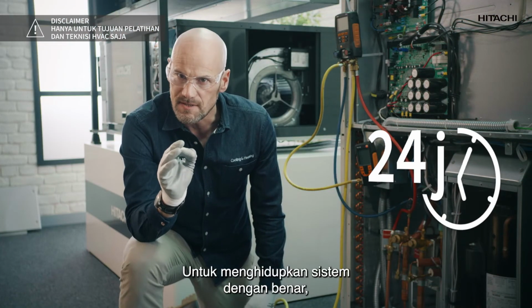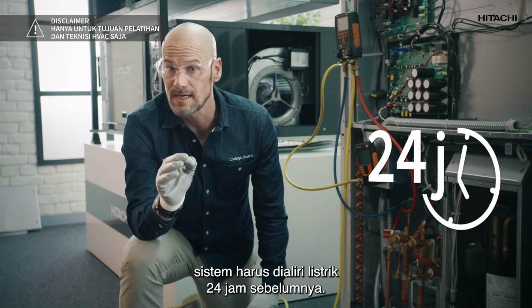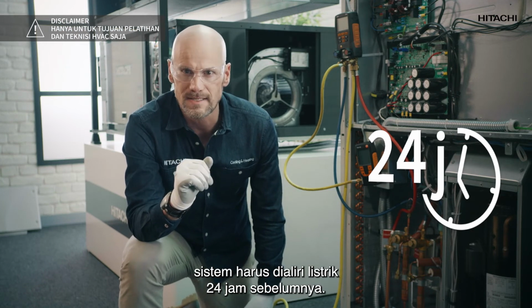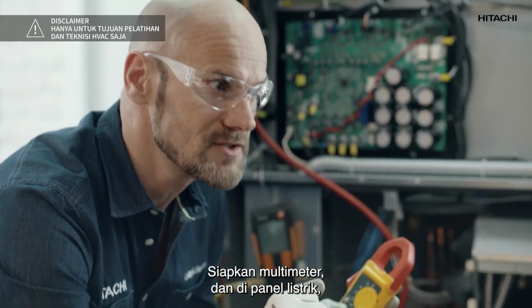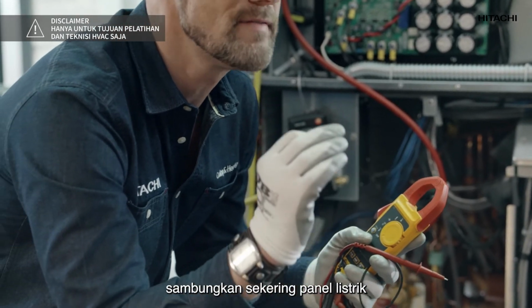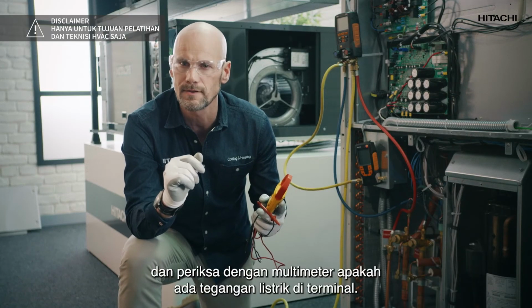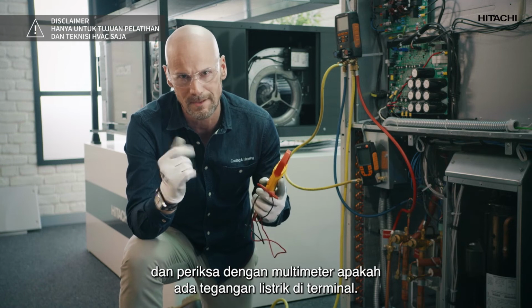To start up the system correctly, it is essential to energize the system 24 hours in advance. We will need a multimeter, and in the electrical panel we will connect the circuit breaker of the electrical panel and check that there is voltage at the terminals with the multimeter.